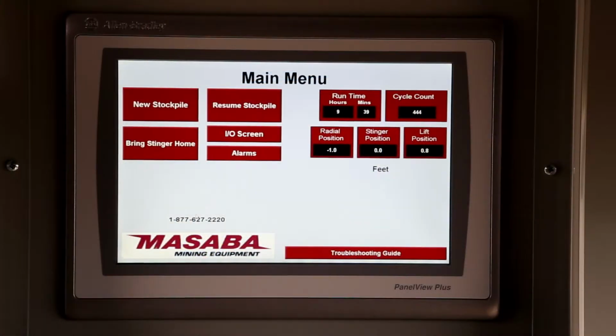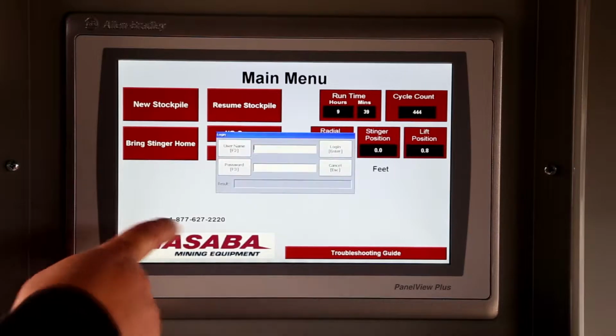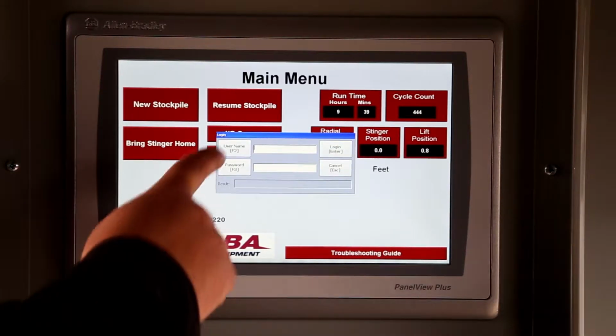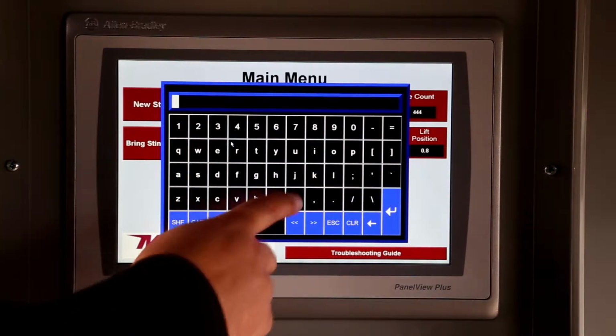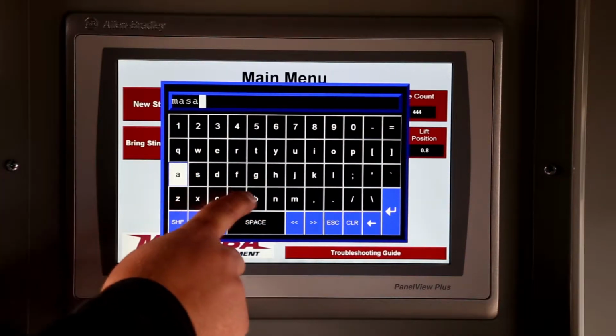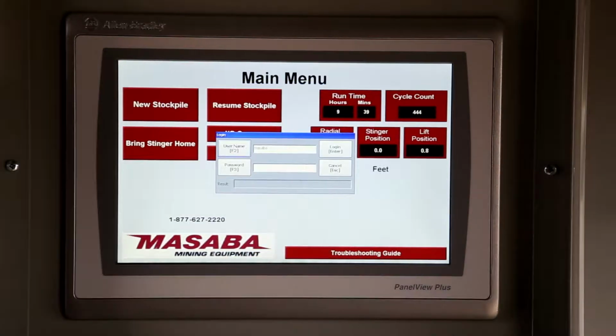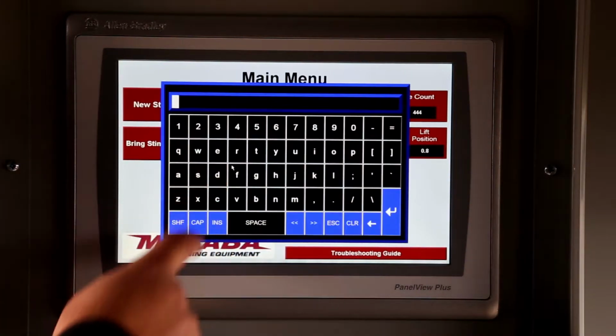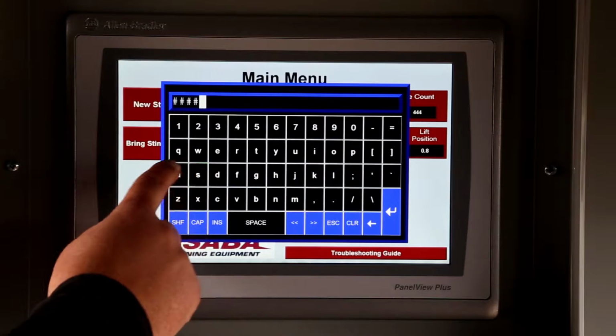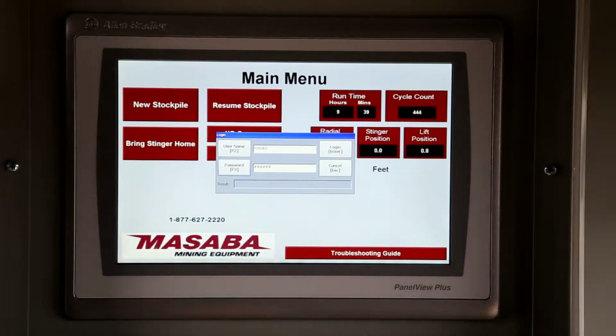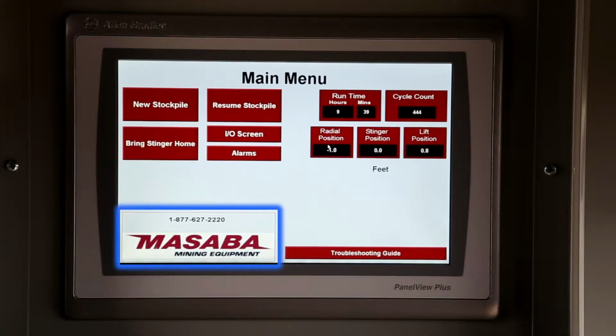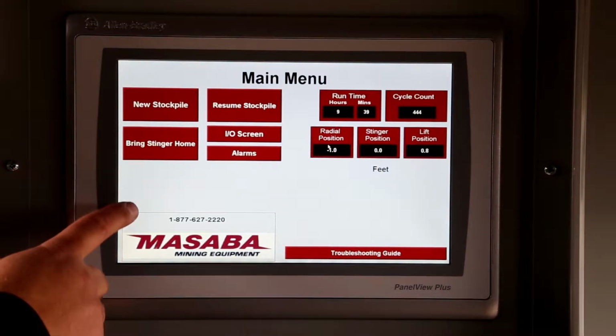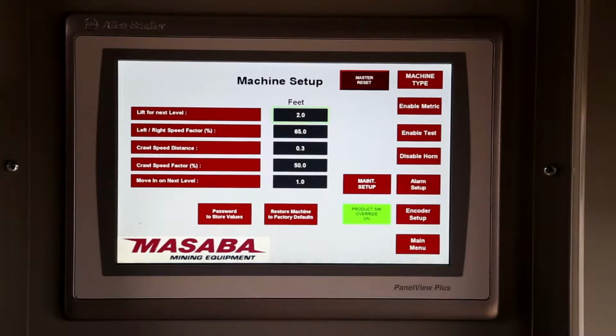the issue. If you need to adjust the calibration, touch the Masaba symbol at the lower left-hand corner of the screen on the main menu screen. This will bring up the login screen. The login username is Masaba, all lowercase. The password is Masaba backwards, Abasam. Touch the login button. There is now a highlighted box around the Masaba logo. Touch the Masaba logo again and go to the machine setup screen.